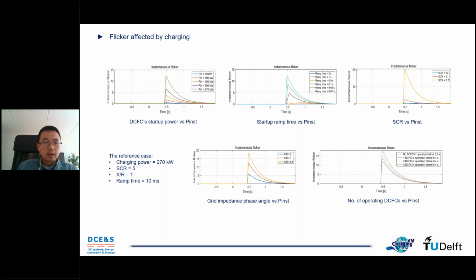So for flicker, we have also done some study about how flicker can be affected by charging. We figured out that flicker can be affected by several aspects of charging, including the startup power, the ramp time of charging, the short circuit ratio of the grid, the grid impedance phase angle - whether it's more resistive or more inductive - and also the status of other chargers in the same station when you start charging with this charger.